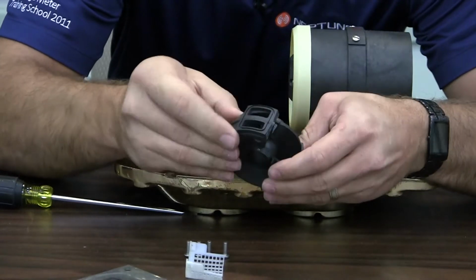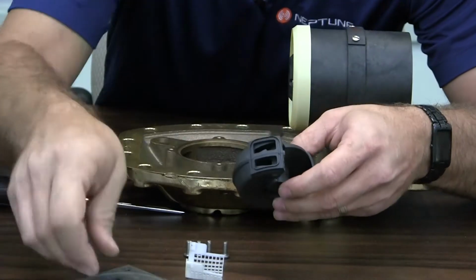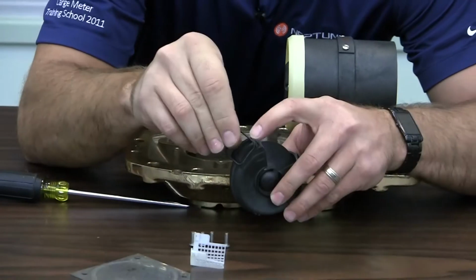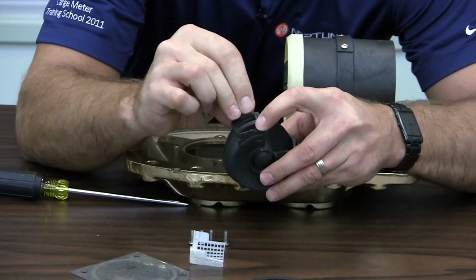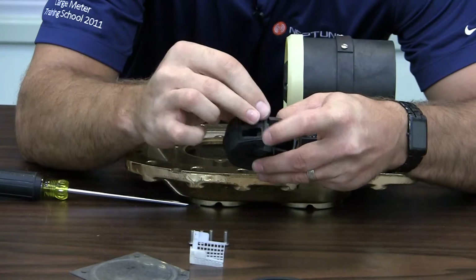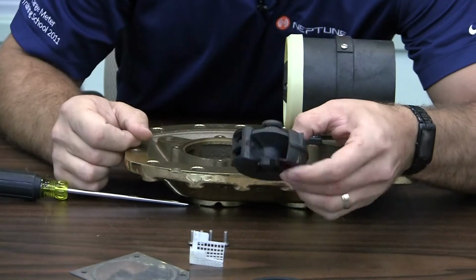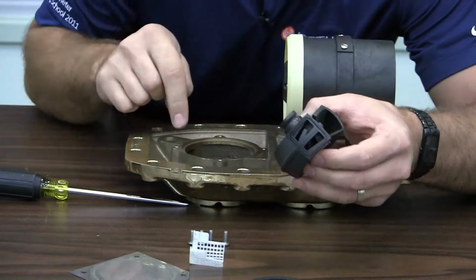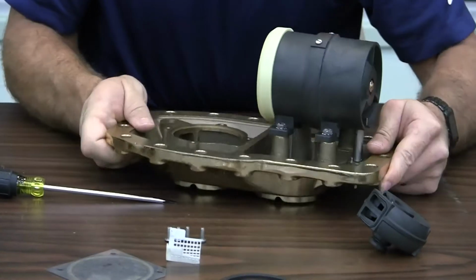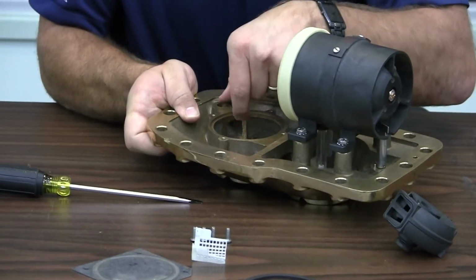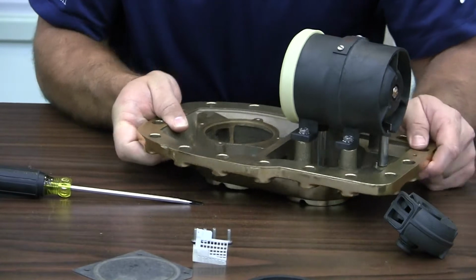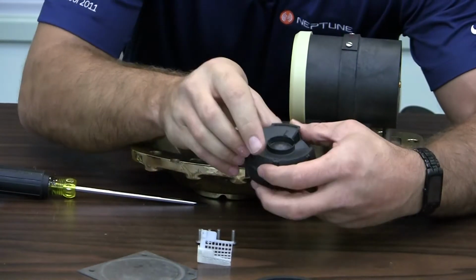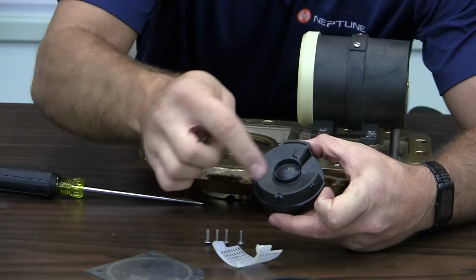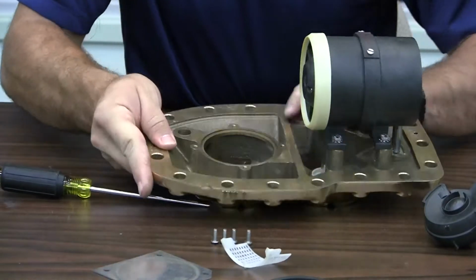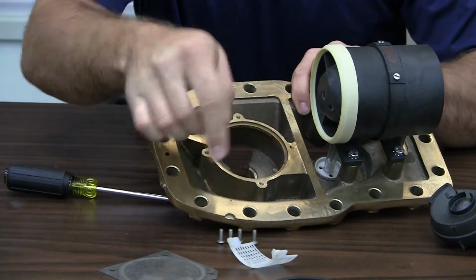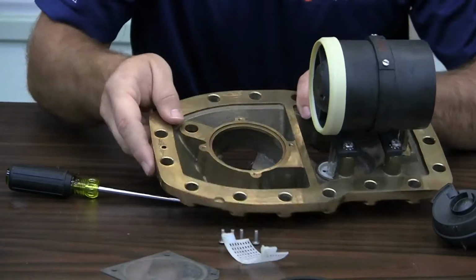Once you get this together, you should hear it snap, and then you can put the gasket back in that seals the chamber to the cover. So all this is together, and you're going to place the magnet facing down. There is a machined surface inside the main case. This is where that gasket rests to form the seal. There's also an opposing notch that we removed the strainer from earlier, and an opposing half moon on the back side that locks in the strainer and the chamber assembly.